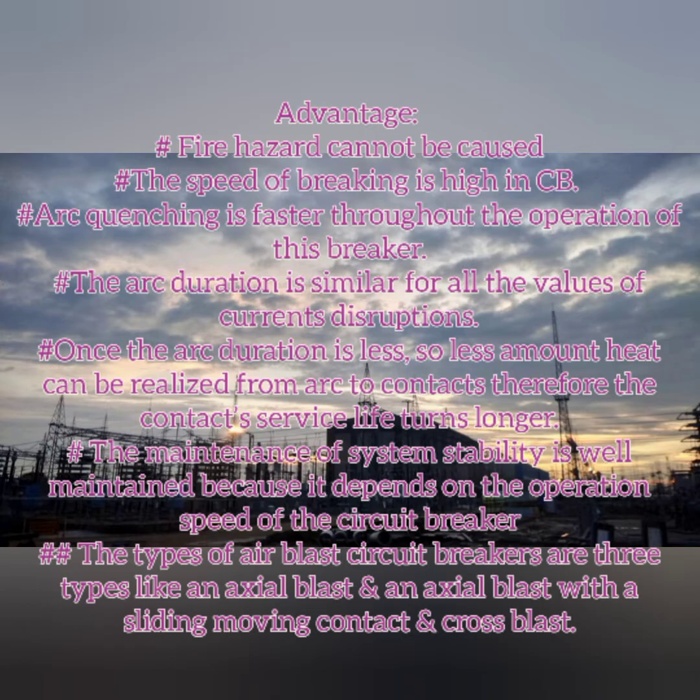So coming up to the advantages of your air blast circuit breakers, it is fire hazard free, which means a fire hazard cannot be caused. The speed of the breaker is very high. Next, arc quenching is faster throughout the operation of the breaker. The arc duration is similar for all values of the current. Once the arc duration is less, less amount of heat is released from the arc to the contacts. Therefore, the contact serves a longer lifetime.